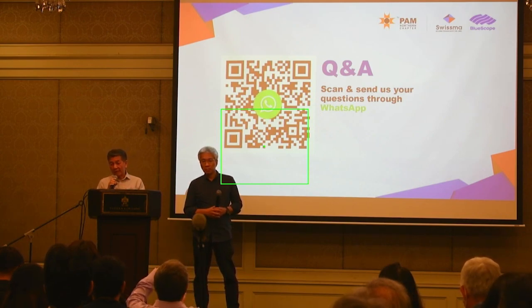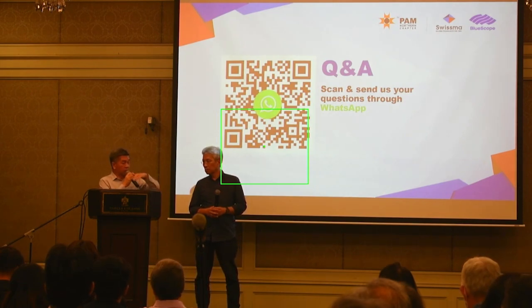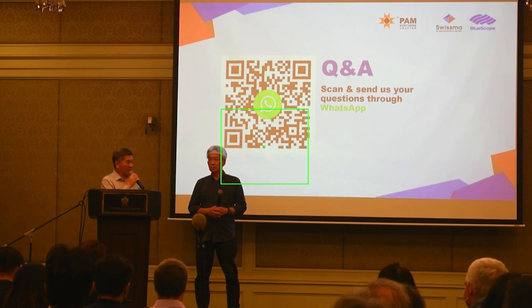A product like this will pass in Part 1 because it can get out of the way, all the fire stops and all that. But that product is not for aesthetic application. So who would want to put this product over a plastered brick wall? So it's totally misleading to say your product passed 8414.